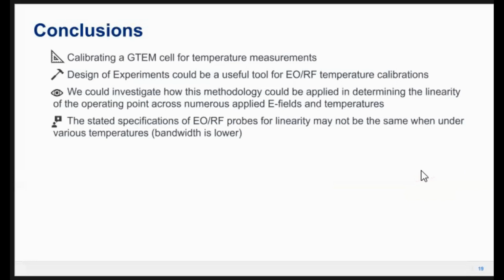And the other aspect about this too is, let's say the manufacturer says this can go up to 20 kV over M or 100 kV over M. You would need to definitely look at the temperature aspect because it may just throw you into a nonlinear regime at a much lower electric field, when you're doing, say, outdoor temperature measurements. So basically, the right tool for the job, and just understanding the different aspects that can affect your calibrations and also the use of these probes.